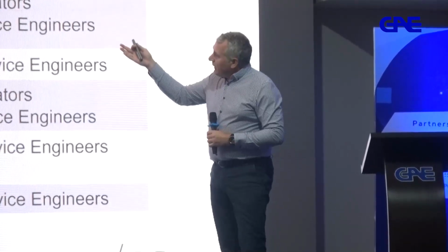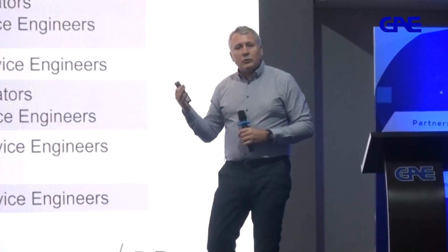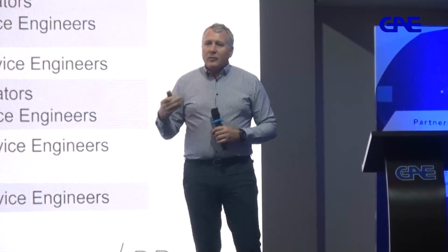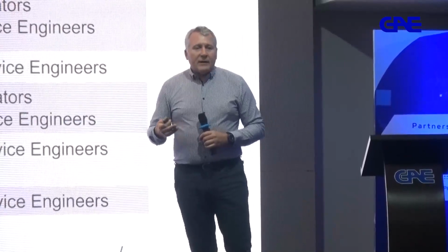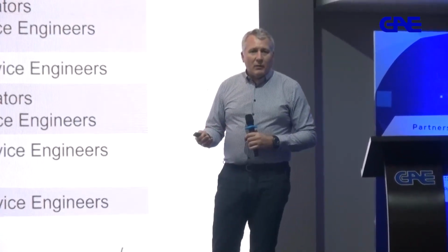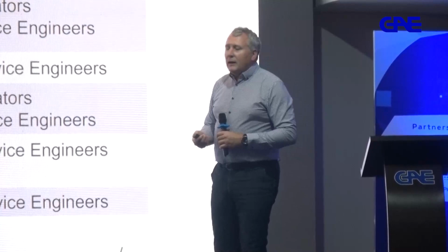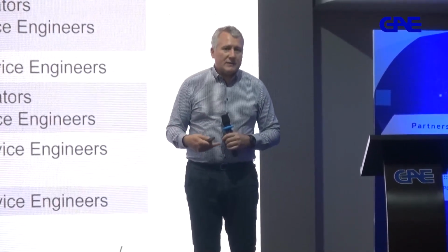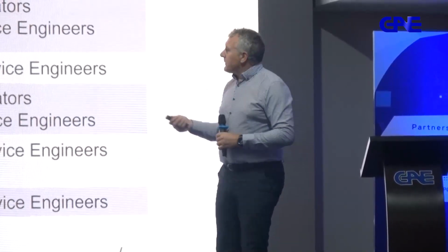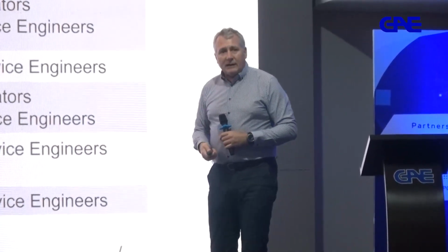So we have here the ability to look from two perspectives at the GIS: from a UHF perspective, and from an acoustic perspective. Funnily enough, the same instrument is used for both, so that's very efficient for you. And naturally, the people using this are commissioning and test engineers, people in the factory, based on the CIGRE guidelines.